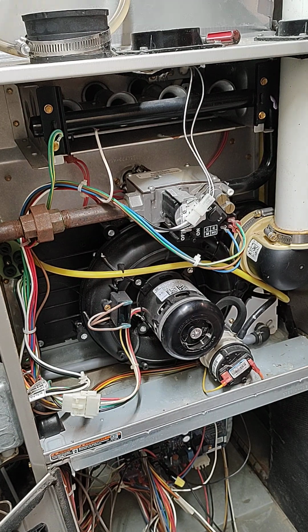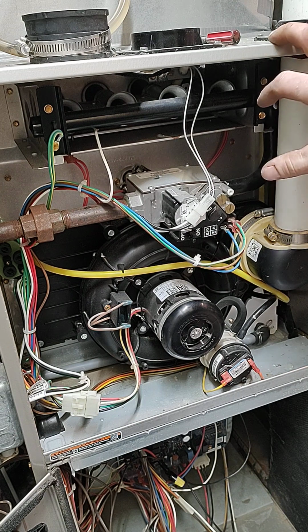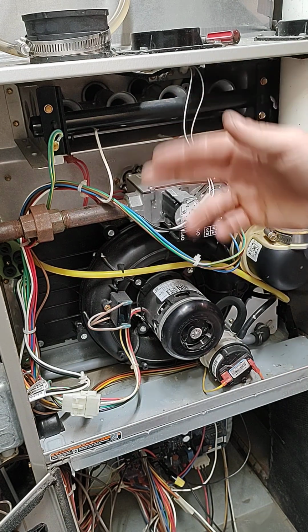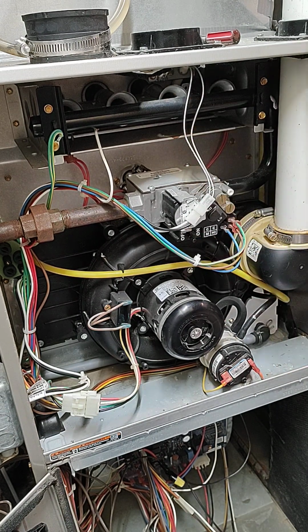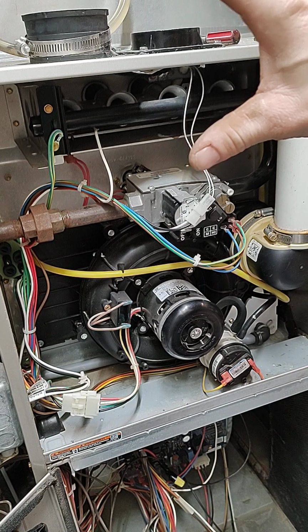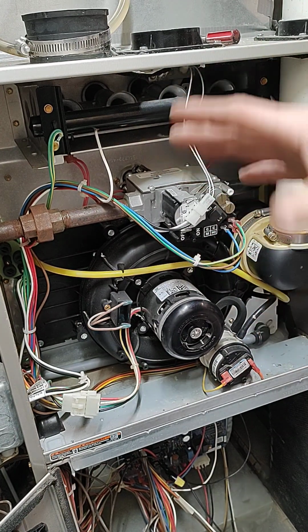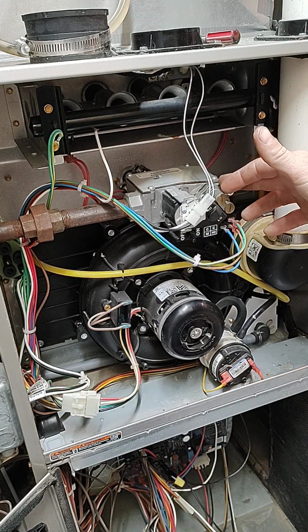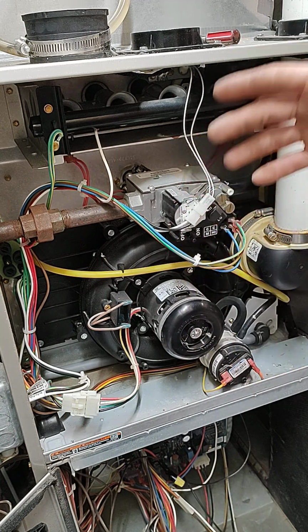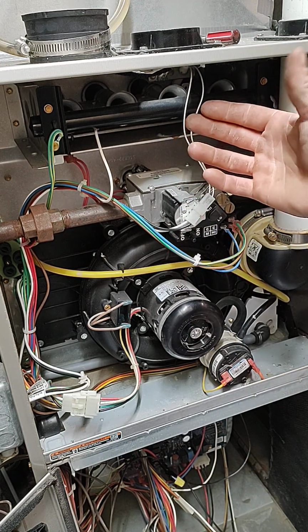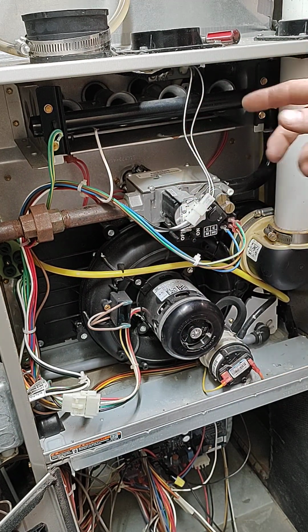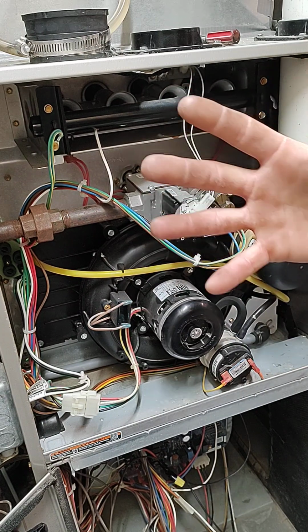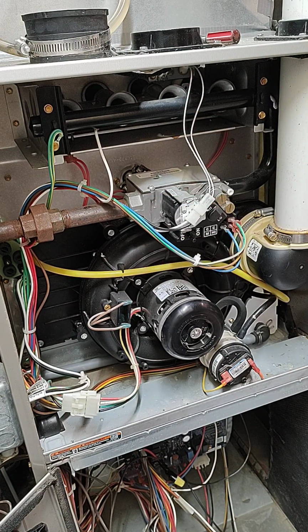When you turn your furnace on, all the flue gas goes through the heat exchanger, gets blown out the pipe, and goes outside, all fine and dandy. But if you don't have air in your house, it's going to try sucking air from outside. So when you turn this off and that fan quits blowing, you're actually going to be pulling air from outside through the exhaust pipe, through the heat exchanger, and blowing flue gas out. Generally it's not a lot, but you don't want carbon monoxide in your house.